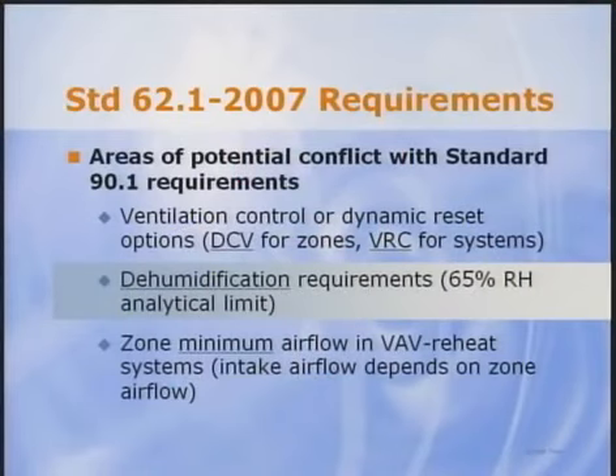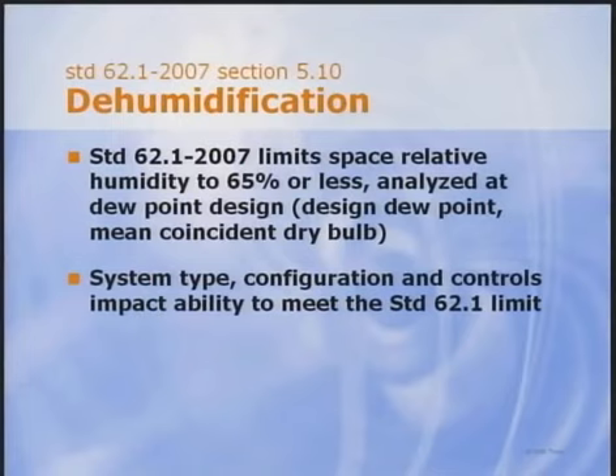High relative humidity indoors can lead to microbial growth on surfaces, so limiting it reduces the potential for IAQ problems associated with mold, bacteria, and general dampness. Standard 62 includes relative humidity requirements. The key requirement is an analytical limit on zone relative humidity whenever the system is dehumidifying. To comply, designers must analyze the performance of the proposed mechanical system at elevated latent load conditions. With outdoor air at the design dew point condition and with no sensible heat gain due to solar load in the zone, a psychrometric analysis must show that zone relative humidity does not exceed 65%.